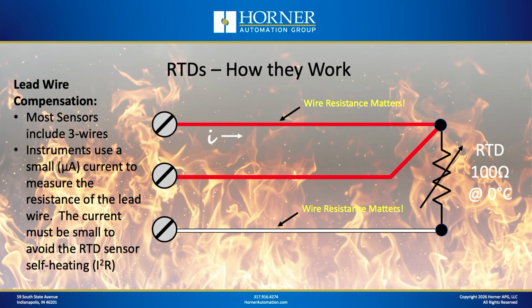And how is that done? Well, it's done through the use of what's called 3-wire or 4-wire RTDs. And in industry, 3 wires are by far the most prevalent. So with a 3-wire RTD, you have an extra wire on one side of the sensor that's used to send out a tiny current. And that tiny current is used effectively to measure the resistance of the lead wire between the measuring instrument or PLC and the sensor itself. So that's how RTD measuring devices can compensate for that lead wire resistance, by having that extra wire. Now, there are also 4-wire RTDs which have a total of 4 wires, but again, in industry, the 3 wires are by far the most prevalent.